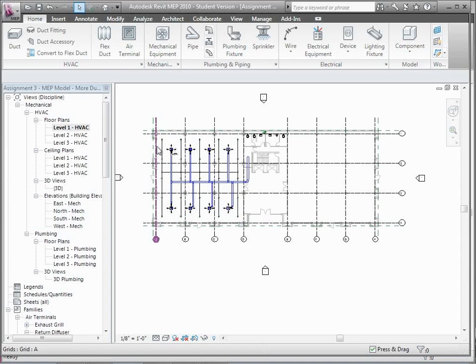For the full system you need one air system that pops out and another that pops in, and there'll be an air handler back here that has a supply side and a return side. Returns are a bit more flexible — for supply we pretty much have to get the air where it wants to go. For returns there are different strategies: sometimes we put in ducts, sometimes we just put in registers and use a ceiling plenum — a space between the ceiling and the floor above — and pull all the air through that, using it like a gigantic duct. That's a really common system.